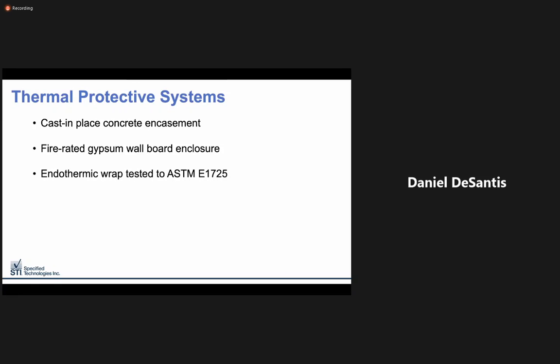Last and not least, endothermic wrap, which is a thin, lightweight material used as the shaft enclosure for protection of the building services. These wraps can provide an hourly rating of up to 2 hours, where traditional means of construction may not be possible. It's important to note that not all endothermic wraps are created equal, and it's imperative that you know the standard to which a particular material is tested before installing.